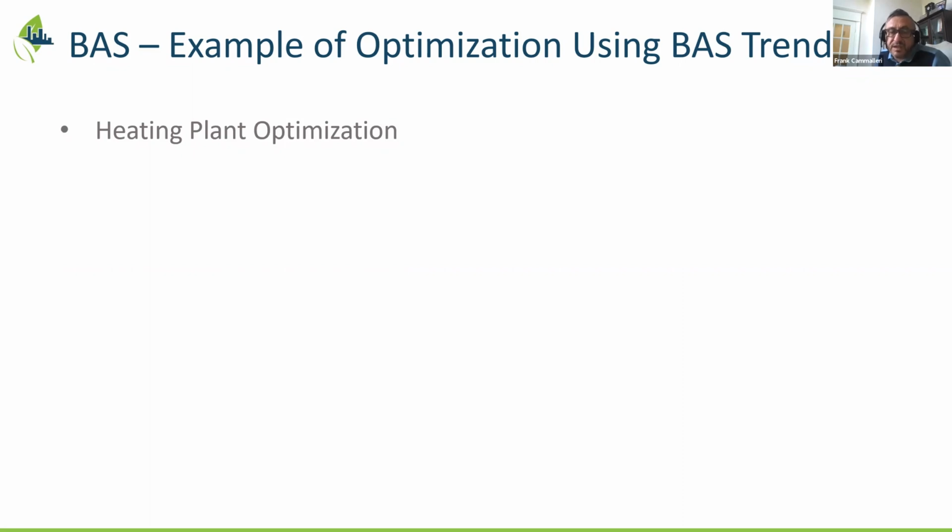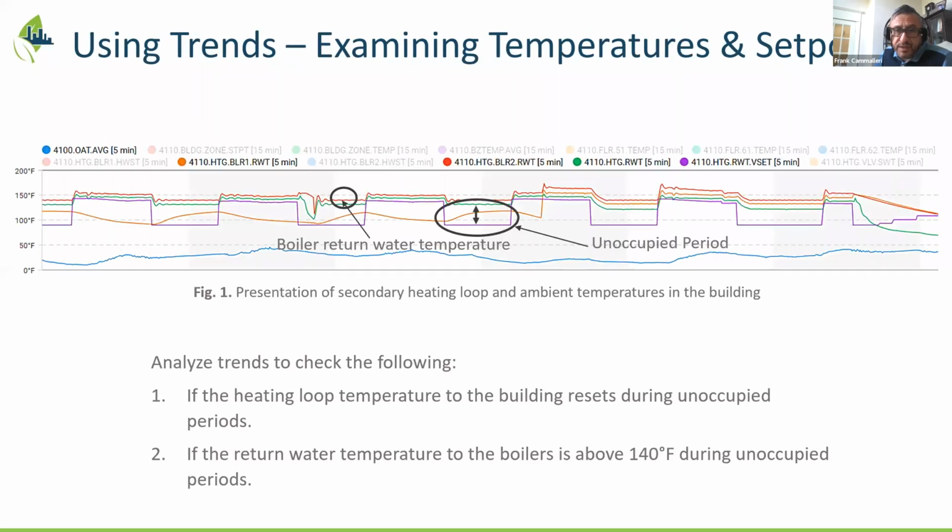So a measure was done in a facility a few years back, and then recent trends from the interval gas data at the building level indicated, wow, there's this big jump in gas usage, and it was occurring over a 3-month period, and we just couldn't figure out what was going on. And so I wanted to stress how this could be useful.